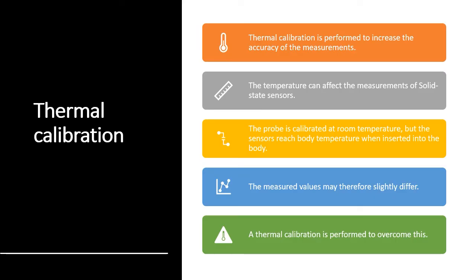A thermal calibration is performed to increase the accuracy of measurements. The temperature can affect the measurements of solid-state sensors. Although the probe is calibrated at room temperature, the sensors reach body temperature when inserted into the body. The measured values may therefore slightly differ. A thermal calibration is performed to overcome this.